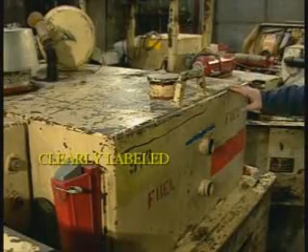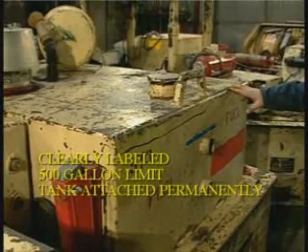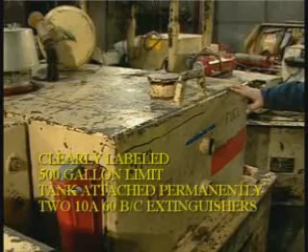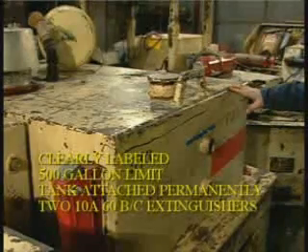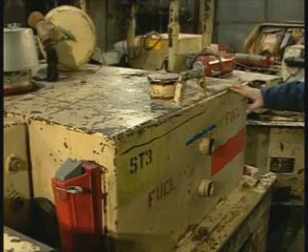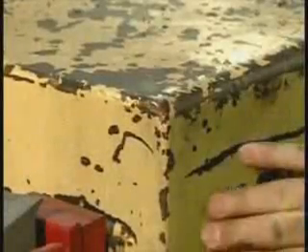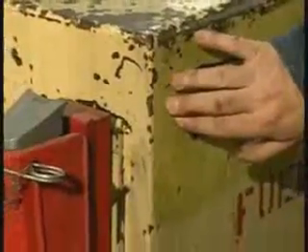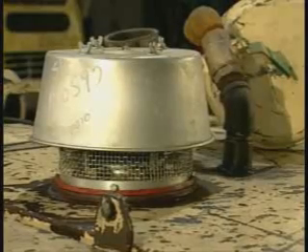It must have a 500-gallon limit. The tank must be permanently fixed and must have at least 2 multi-purpose dry chemical fire extinguishers that are 10A60BC or higher rated. Diesel fuel tanks must not leak. Wall thickness must be a minimum of 3/16 of an inch. It must be protected against corrosion and be of seamless construction or liquid-tight welded seams. Tanks must also have devices for emergency venting of at least 4 inches or greater diameter.